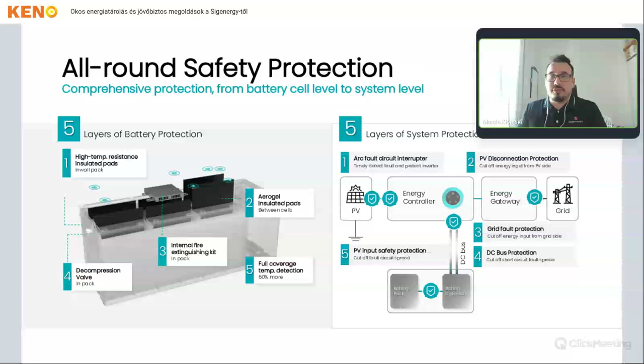From reliability of the system and warranty, there's a common question about how many cycles it can work. Generally we changed the cells to 314 at this moment. The manufacturer of the 314 ampere cells, which is CATL at this moment, EVE or REPT, provides confirmation that the estimated cycle number is 10,000. By end of life of this battery we define 60% state of health - so from the preliminary or beginning capacity, if the battery reaches 60% of that, it's end of life. In the meantime, it can do even 10,000 cycles.